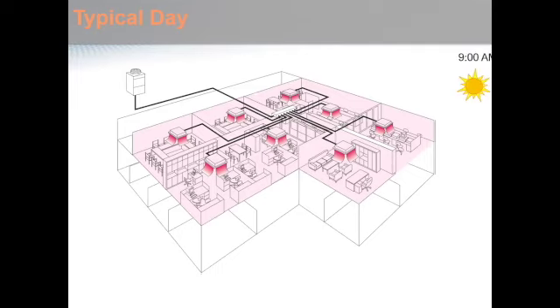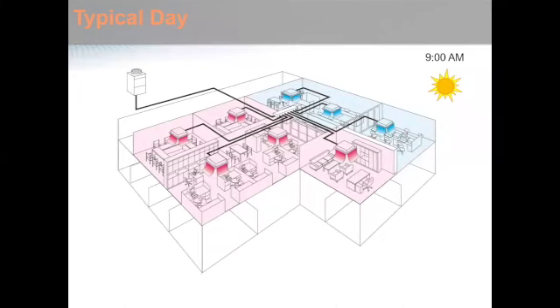As the day moves on, we get to 9 a.m. Everyone is coming into the office. We have that eastern facing facade over here. That zone, because of the solar load coming into it, is going to be heating up a lot more quickly than the other zones in the space. So what that BC controller over there is going to allow us to do is provide cooling to those zones, but allow the other zones that are not yet up to set temperature to maintain their heating and stay in heating mode.